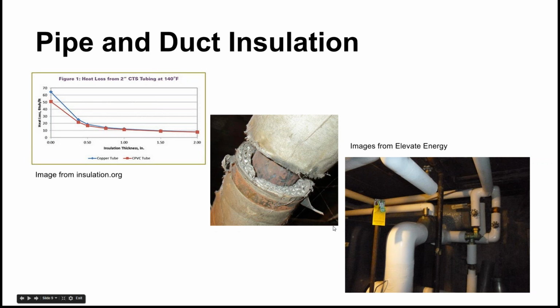And this is a good example of how much pipe is around that can be insulated. It's just everywhere in this picture. And this is for a steam system. It's making sure that the steam is actually getting to the radiators, it's not condensing before it gets there, and that helps keep the building heated more evenly. It helps make sure that the steam doesn't condense into water before it gets there, and therefore it prevents all sorts of problems.